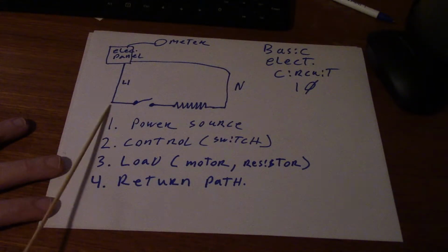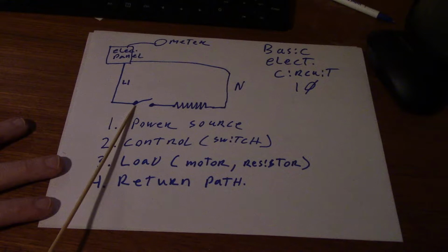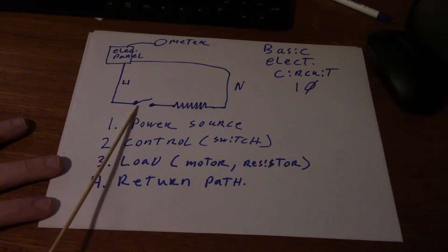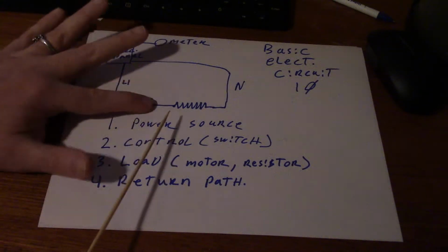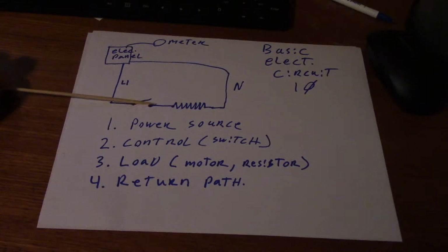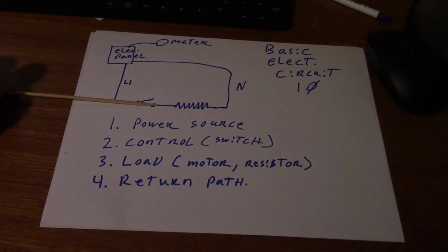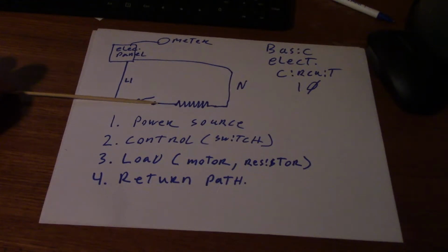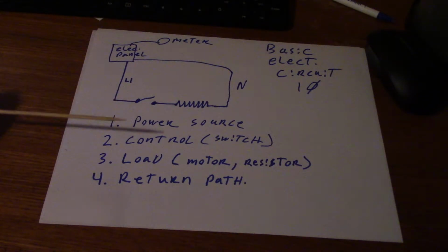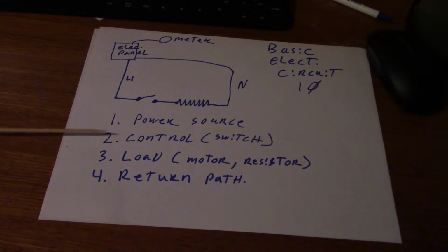You have to have a switch on the circuit, because if you take that out and just make a straight connection, you cannot control, in this case, a resistive heater. The heater would be on 24/7, 365, until something burns out or poops out, because you have to have a way to control that load.